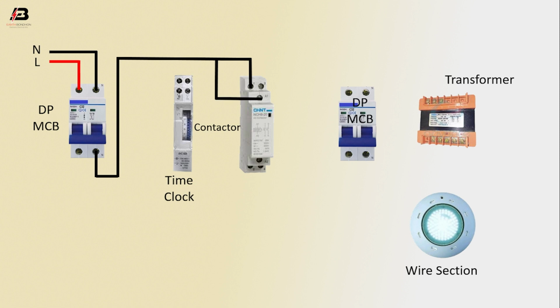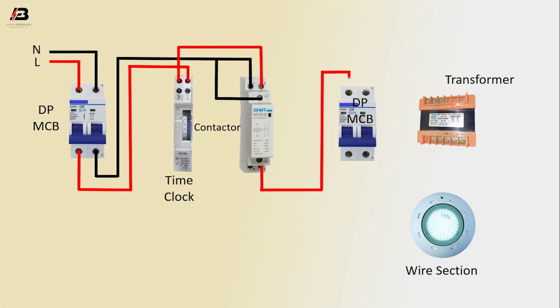Phase connection from DP MCB to connect time clock, output connection from time clock to connect contactor, output connection from contactor to connect another DP MCB, output neutral connection from contactor to connect another DP MCB.